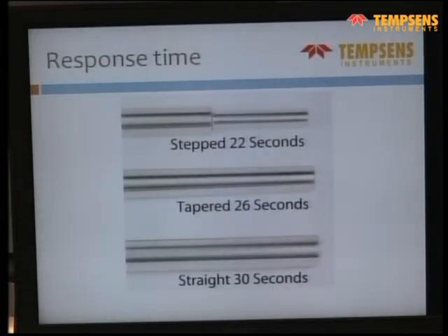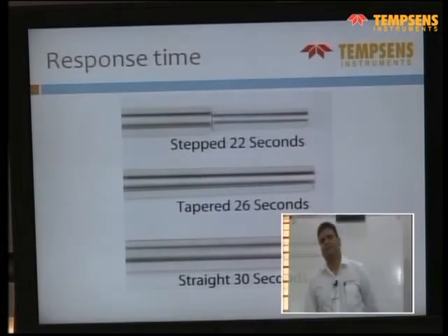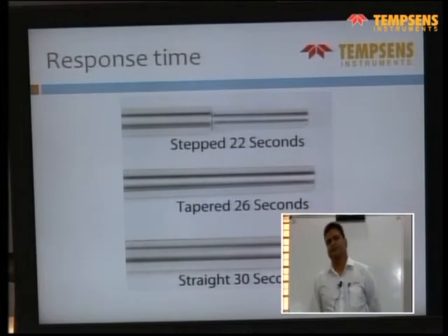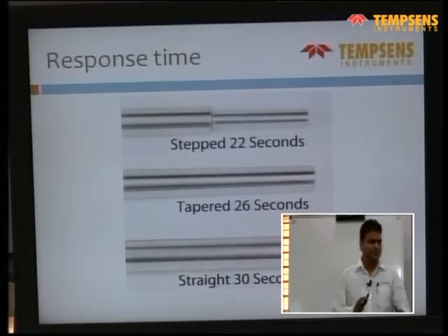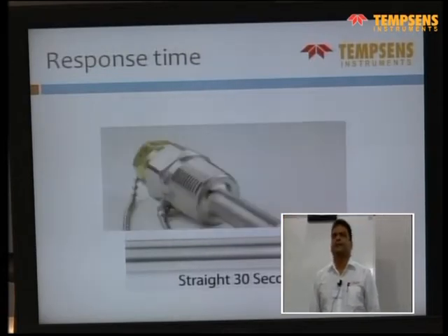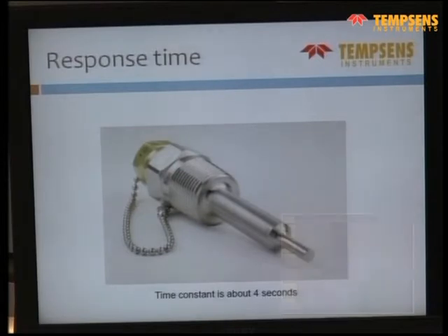Response time, as we already discussed: for this stepped thermowell we got around 22 seconds response time. For a taper it was 26, and for straight it was 30 seconds. So this depends on the type of design of your stem. If you want fast response time, you can go for a very small tip. The sensor can also be welded directly onto the thermowell, which gives strength to the whole length of the thermocouple, and then only the tip comes out. Or you can have an insertion with a smaller tip.